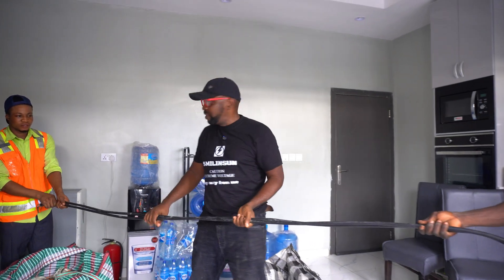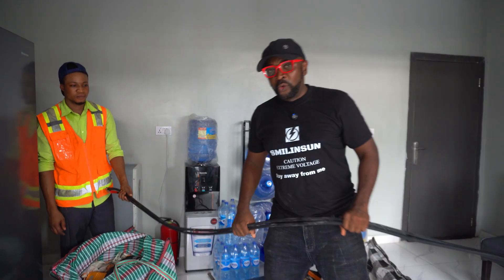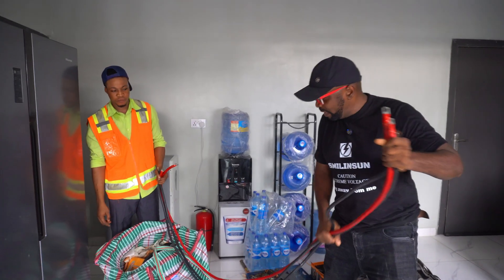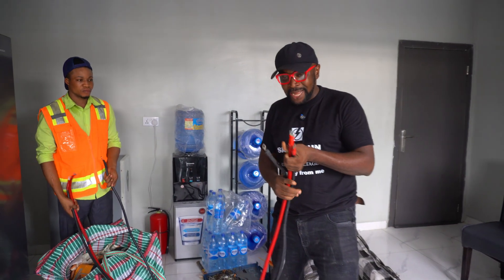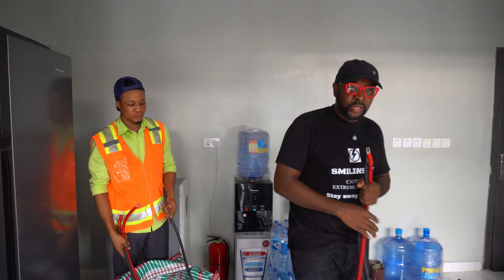There are essentially four batteries connected in parallel here. If the cables aren't the same length and precision, you'll notice charging differentials. The owner has expressed concern — some batteries charge fully while others lag behind. One major culprit is unbalanced cable lengths, causing uneven charging and discharging. So we took the shortest cable as the sample and cut every single one to that same precise length so none is at a disadvantage and all receive energy at the same time.